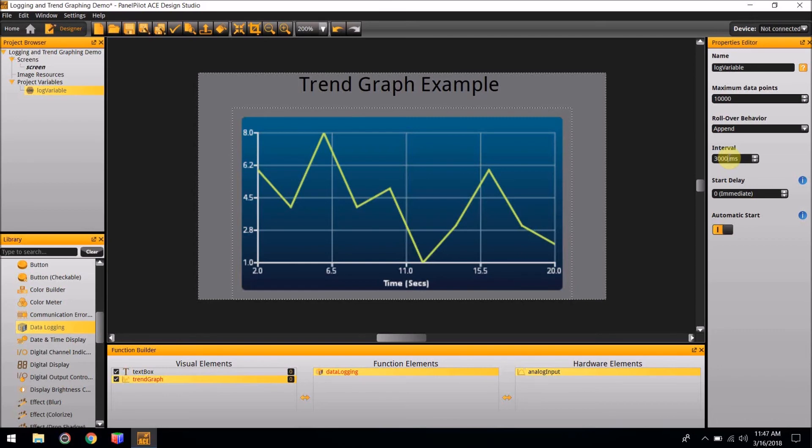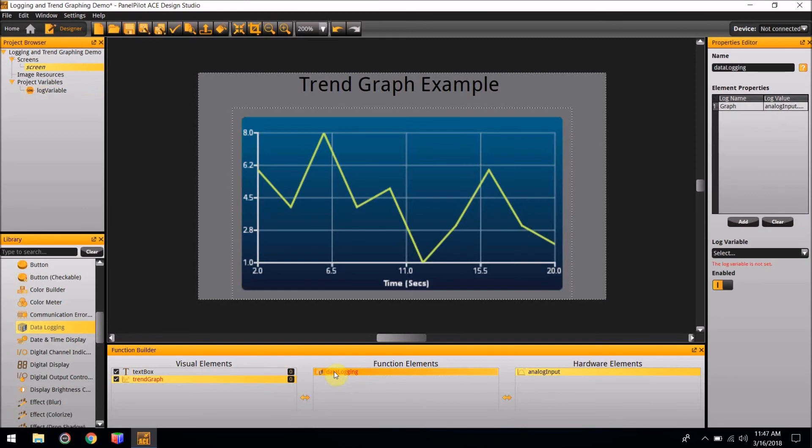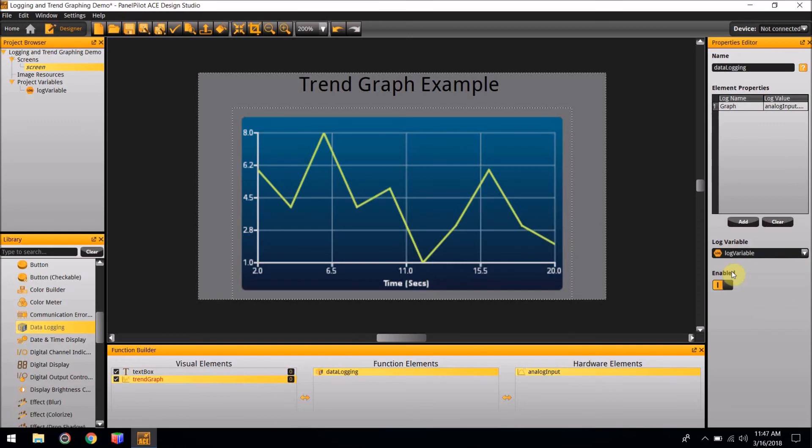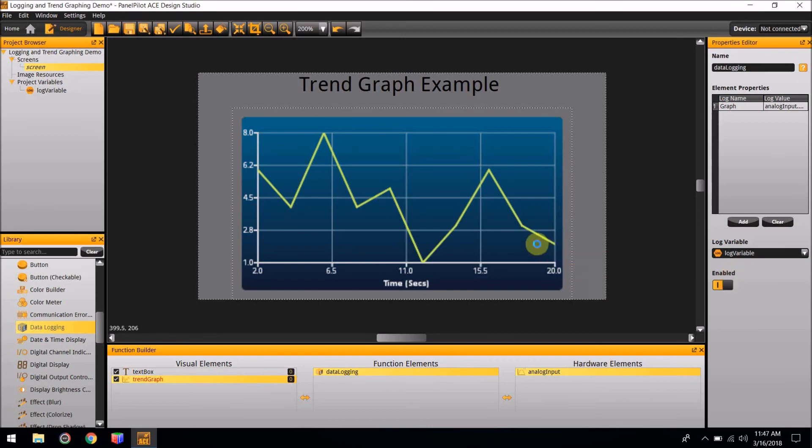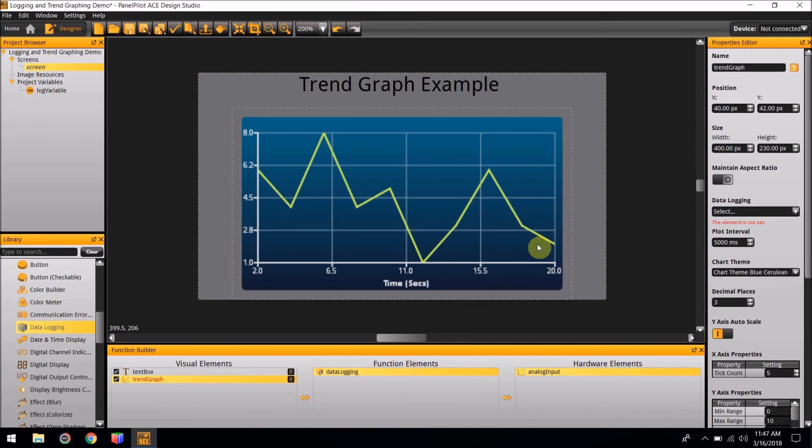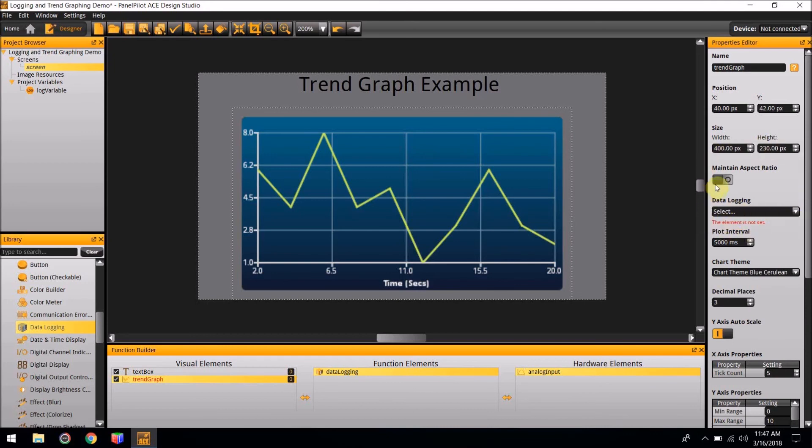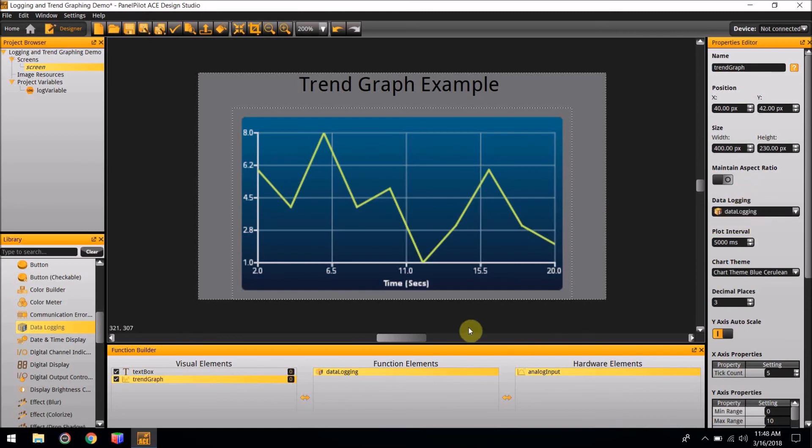Now if you go back to the data logging function element, you can add this log variable to the Log Variables section. This step is now complete. To finish the project, we need to tie everything we just made together with the Trend Graph. Click on the Trend Graph to bring up its Properties Editor. In the Data Logging section, halfway down the Properties Editor, click on the arrow and select the Data Logging feature we just created. The project is now complete.